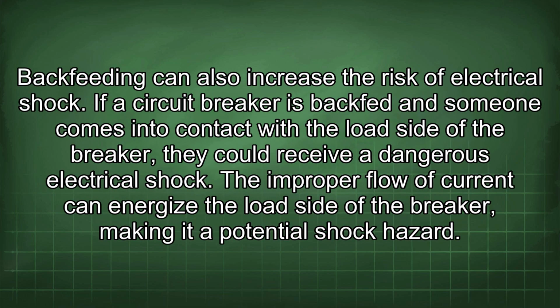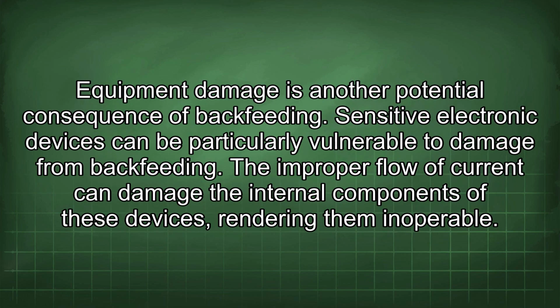Backfeeding can also increase the risk of electrical shock. If a circuit breaker is backfed and someone comes into contact with the load side of the breaker, they could receive a dangerous electrical shock. The improper flow of current can energize the load side of the breaker, making it a potential shock hazard. Equipment damage is another potential consequence of backfeeding. Sensitive electronic devices can be particularly vulnerable. The improper flow of current can damage their internal components, rendering them inoperable.